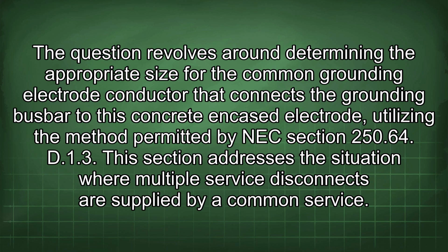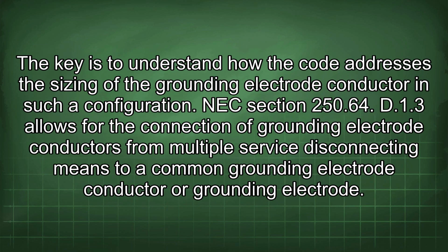The question revolves around determining the appropriate size for the common grounding electrode conductor that connects the grounding busbar to this concrete encased electrode, utilizing the method permitted by NEC section 250.64(D)(1)(3). This section addresses the situation where multiple service disconnects are supplied by a common service. The key is to understand how the code addresses the sizing of the grounding electrode conductor in such a configuration.